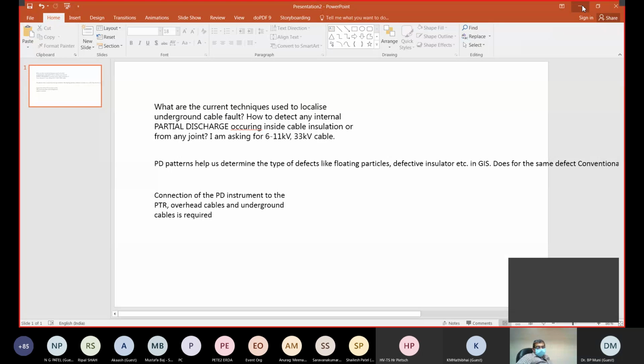Now the next question: is lightning impulse or switching impulse test recommended for on-site testing as condition monitoring? If yes, what is the test voltage and is the waveform the same as mentioned in the standard? To my knowledge, it's not necessary for both GIS and transformers. It can be done in addition, but it's not recommended because you need much more equipment. For a GIS, due to the higher capacitance, you normally accept oscillating lightning impulse or oscillating switching, and the values and the frequency components are defined in the standard 60060-3, and this has to be fulfilled, but it's an add-on.